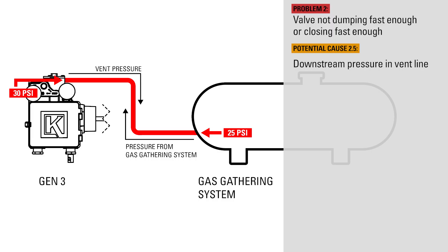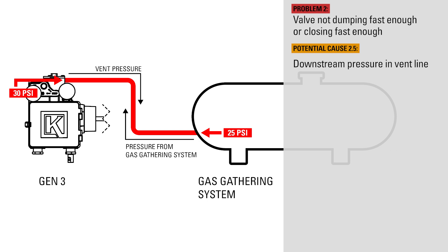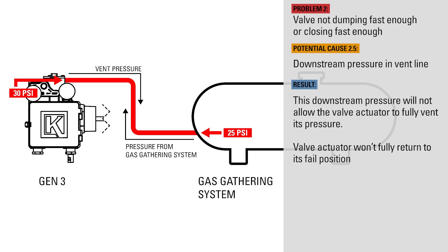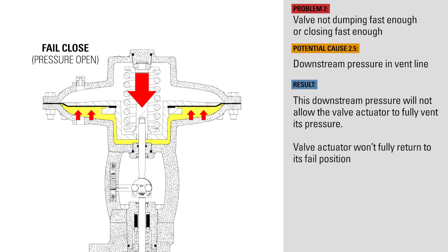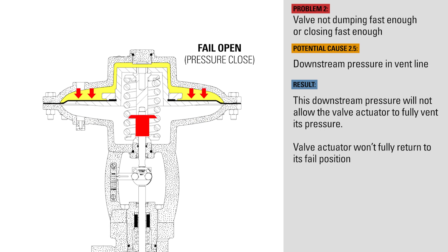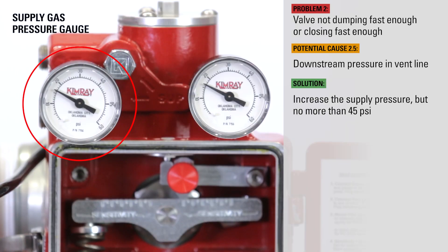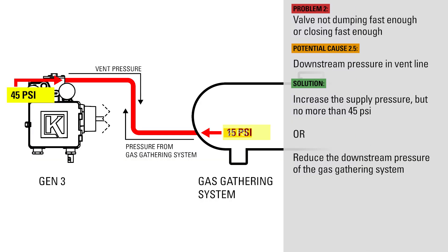If there is pressure downstream in the vent line due to a gas gathering system, the venting rate could be slower than normal because it's having to push against the downstream pressure as it exits the controller. Additionally, this downstream pressure will not allow the valve actuator to fully vent its pressure. If connected to a fail closed valve, there's a possibility the valve won't close fully if the actuator spring doesn't have enough force to act against the remaining pressure. For the same reason, a fail open valve might not be able to open fully. Increase the supply pressure, but no more than 45 psi, or reduce the downstream pressure of the gas gathering system.